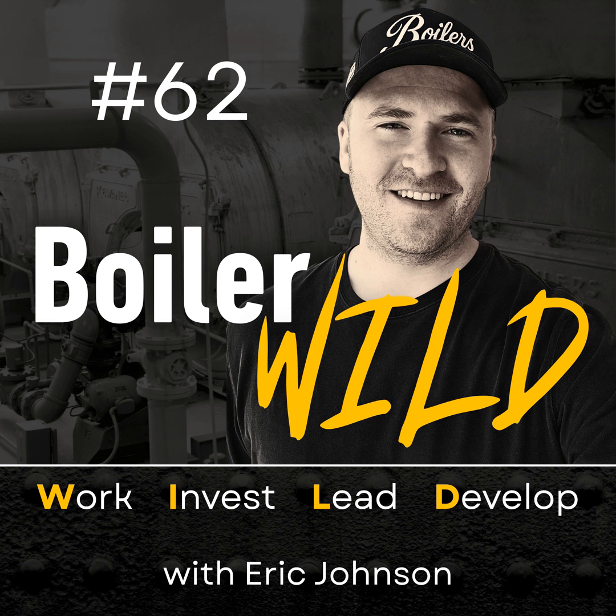If it fluctuates a ton, that may be an issue, because if the customer has 6 boilers and 4 water heaters, maybe it's a hotel, and when all the water heaters come on in the morning when everybody's taking showers and all the boilers are still running hard because it's a cool morning, they're running out of gas and they have a gas issue or something like that. So is the gas dynamically stable? So is it dropping more than 20% when all the equipment is off versus when equipment is on?